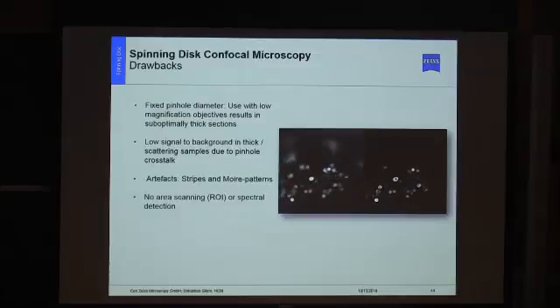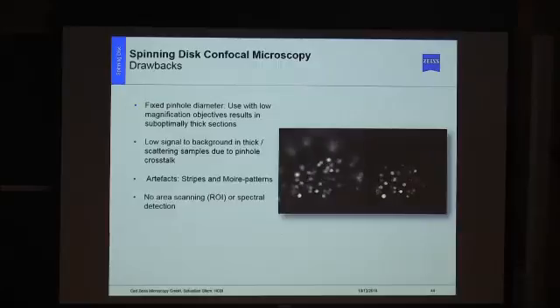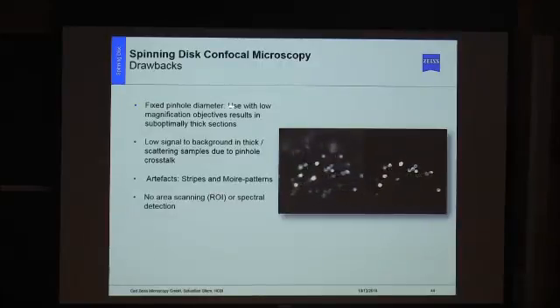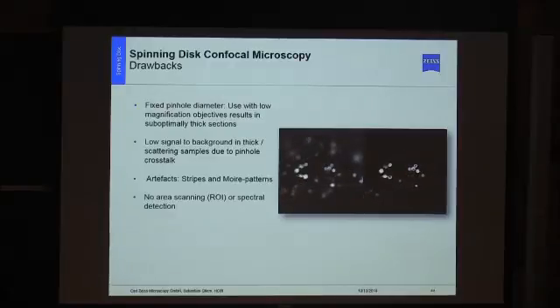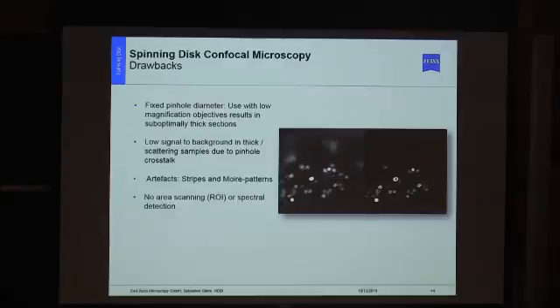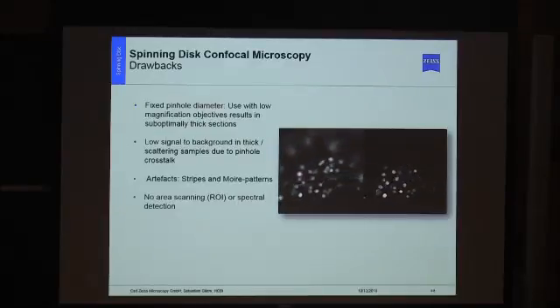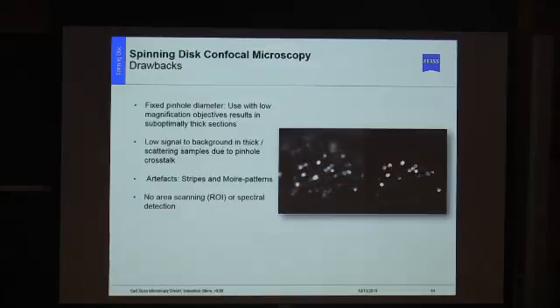Drawbacks of the spinning disk system: the pinhole inside the disk is fixed — you can't change it. This means that if you use low-magnification objectives, your images will result in suboptimal, thick optical sections, so you won't achieve the highest optical section quality. You will have low signal-to-background in some examples. And you might get some stripe-like artifacts in the images.